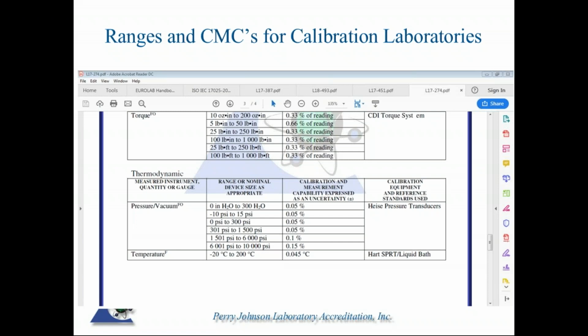Next column over, we see calibration and measurement capabilities, and it says expressed as an uncertainty. So what that is, it is uncertainty. However, it's the best uncertainty that that organization can produce. Hence, let's say if this organization had 0.2 degrees C under there, 0.045 is pretty good. To say it was 0.2, and your protocol or your procedure calls for 0.1 degree accuracy, this client's not going to be able to provide that under their accreditation.